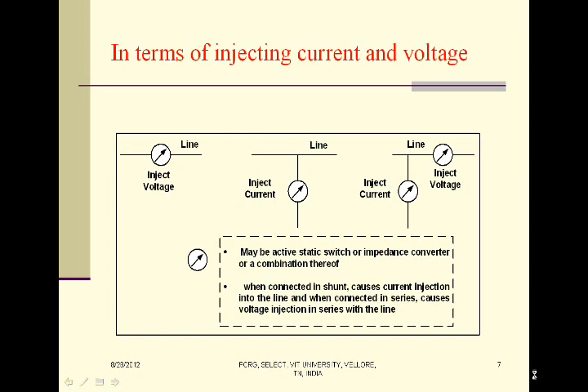The main forms of compensation are in two types: shunt and series. The third form is a combination of both series and shunt. If we connect the compensator in series with the transmission line, then the compensator injects voltage into the system, thereby controlling the line current. By connecting a shunt compensator into the system, it injects current into the system, thereby controlling the voltage at the connected point. A combination of both series and shunt will control both real power as well as reactive power in the system.